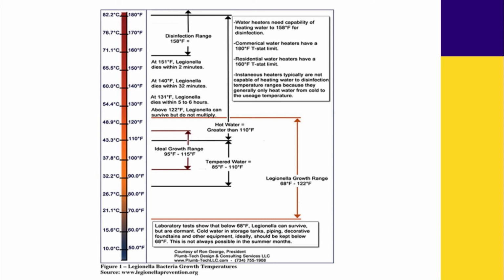So there's a double whammy going on. Not only are you providing hot water, but you are also flushing away those bacteria. And it's important to have a certain contact time with that temperature in order for it to be effective. Now, you can't turn all your spigots on at once because you're running out of hot water. So it takes some thought, and that's part of the water management team and their evaluation.